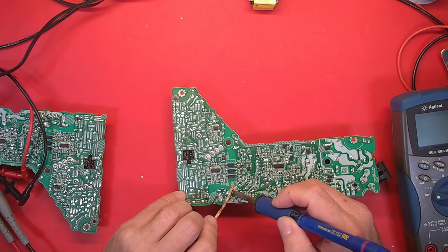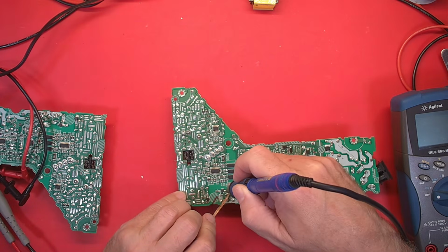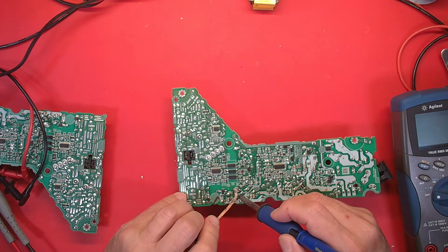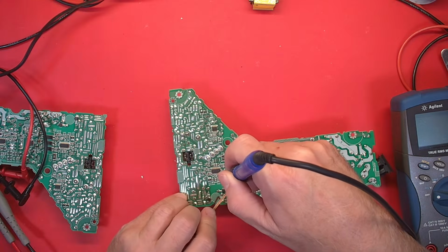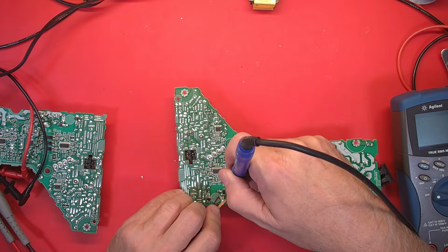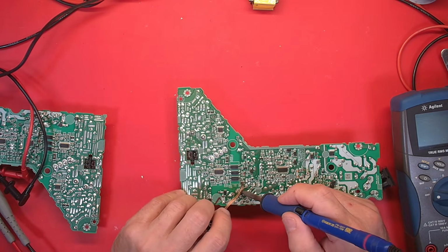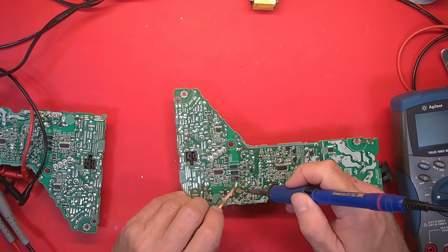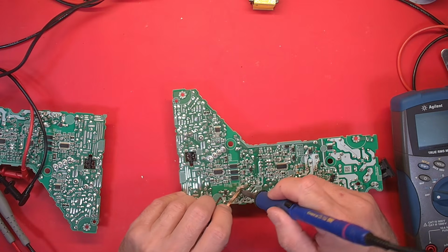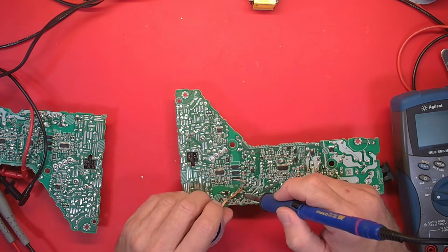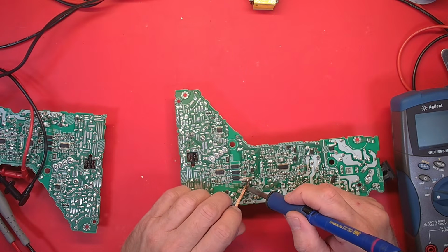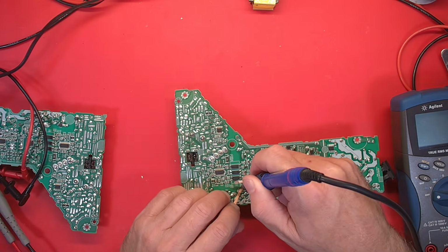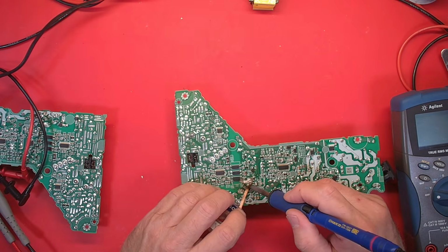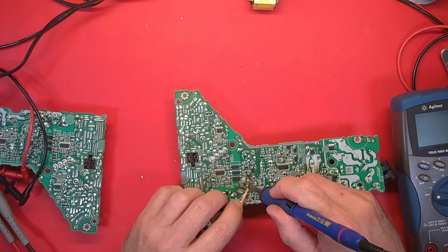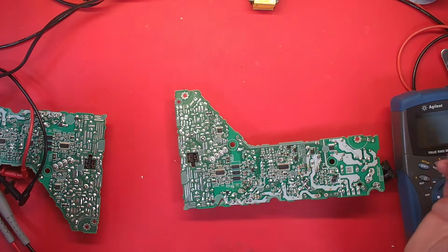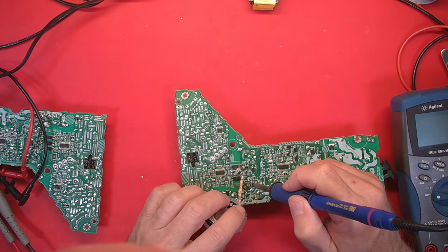But yeah, this is the one from yesterday that was unstable at certain currents. 5 amps it was fine, 10 amps it was fine. You started getting like 15, 16 amps, and it got very nervous. The PFC voltage got nervous. Now the output's still working fine, it's still putting 12 volts out like nothing, and I don't think it even varied any. The output did not, but that PFC voltage varying around like that, shooting up, it never went into the danger area, you know what I'm saying? It didn't go to 450 volts or anything exceeding the voltage of the capacitor. But it should not be nervous like that. It should really just sit there at 394, 395, 396, and maybe vary a volt.